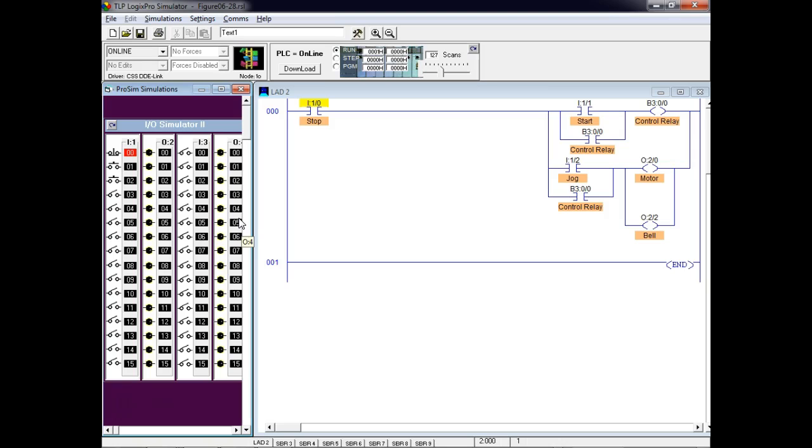So every diagram that he's drawn from then on, when he hooks it up to the PLC, he uses a normally closed stop button. But then in his program, he uses the examine if open instruction. Doing kind of like everybody else is doing. Well, the PLC that he's playing around with probably has nothing but normally open push buttons on it anyway. So if the trainer you're playing with has nothing but normally open push buttons, then you've got to use that, right? You understand? But it's a trainer. It's not in real life. In real life, that button is going to be a normally closed push button. So I guarantee you that's what he did.